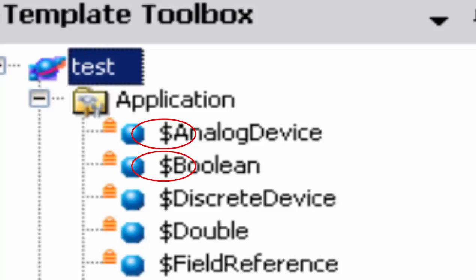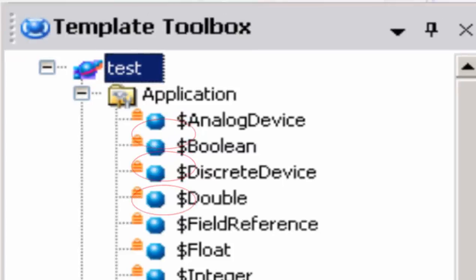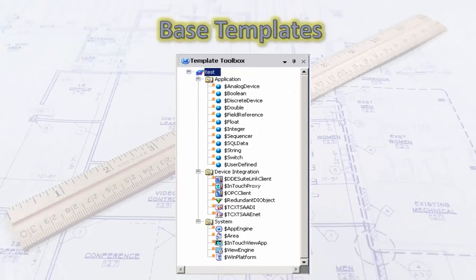Now I want you to notice something about all of these templates: there's a dollar sign in front of the name. When you see a dollar sign in front of the name in ArchestrA, that's a template — these are the blueprints or cookie cutters for the different types of objects. So when you create an object from the analog device template, it'll be an analog device object and it'll take on all the characteristics of that parent template.